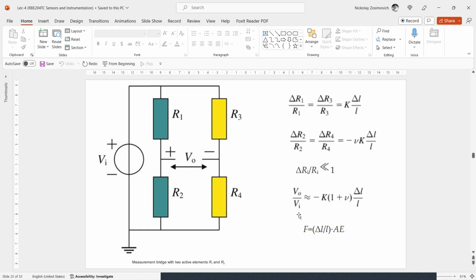What we may see in this equation is that the applied force should usually be found using Hooke's law, or rewritten in terms of force and deformation. F is proportional to delta L over L times AE. Here A is the cross-sectional area of the bar, and E is Young's modulus of the material, or sometimes the elasticity C. But we should note here that due to the Poisson ratio of the spring element, the compensating strain gauges in the transverse direction contribute significantly to the bridge output. With strain gauges mounted directly on a construction part, the same relation holds between the bridge output and the force applied.